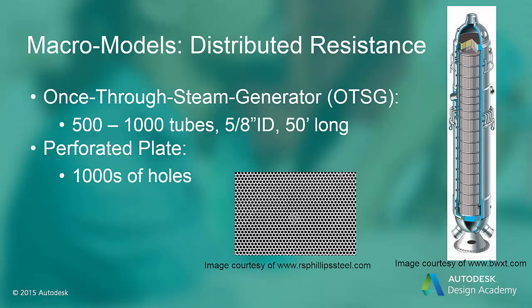Here are two examples of why we need to use macro models. In the OTSG there are hundreds or even thousands of tubes that make up the steam generator. To mesh just one tube would require a mesh with 5000 nodes. Multiply this by 500 tubes and the mesh now has 2.5 million nodes just for the tubes. To mesh around each tube would require at least twice that many nodes, and you can see how the mesh would grow rapidly if we tried to model each tube individually. The same rapid mesh growth would result when trying to mesh the perforated plate shown.